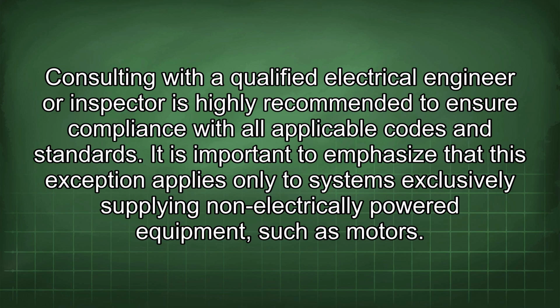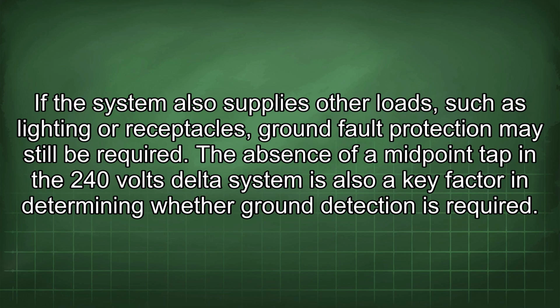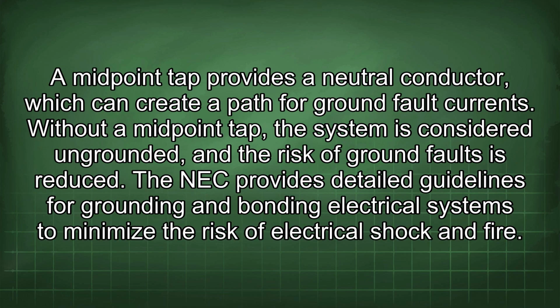It is important to emphasize that this exception applies only to systems exclusively supplying non-electrically powered equipment, such as motors. If the system also supplies other loads, such as lighting or receptacles, ground fault protection may still be required. The absence of a midpoint tap in the 240 volts delta system is also a key factor in determining whether ground detection is required. A midpoint tap provides a neutral conductor, which can create a path for ground fault currents. Without a midpoint tap, the system is considered ungrounded, and the risk of ground faults is reduced.